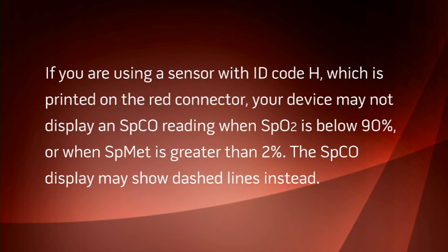Elevated levels of methemoglobin will lead to a falsely elevated SpCO reading. This can be measured with SpMet, non-invasive methemoglobin. If you are using a sensor with ID code H, which is printed on the red connector, your device may not display an SpCO reading when the SpO2 is below 90% or when SpMet is greater than 2%. The SpCO display may show dashed lines instead.